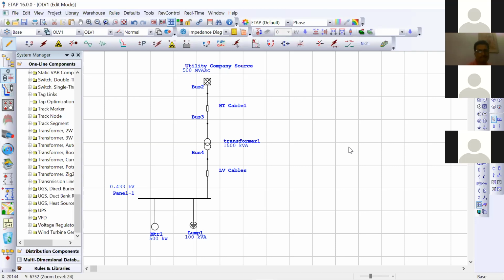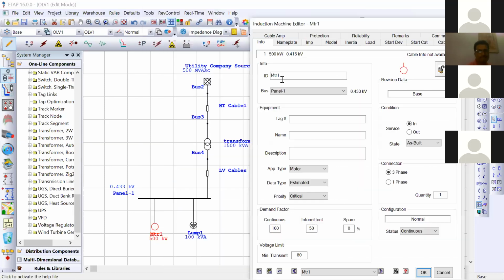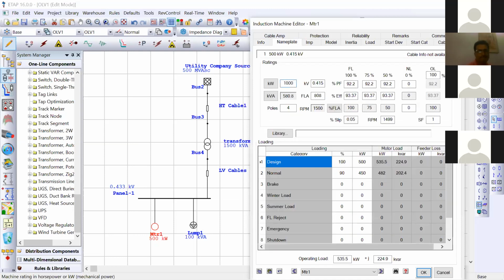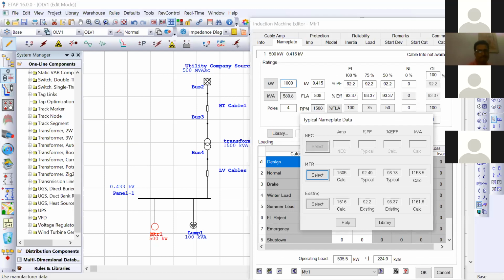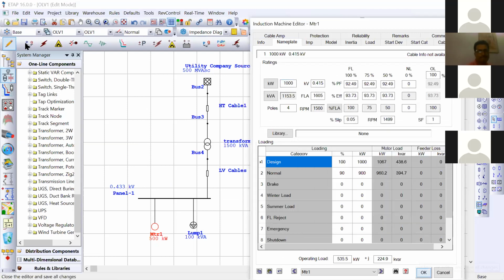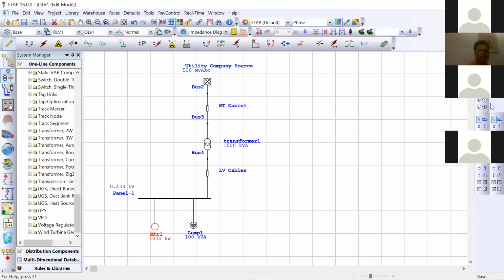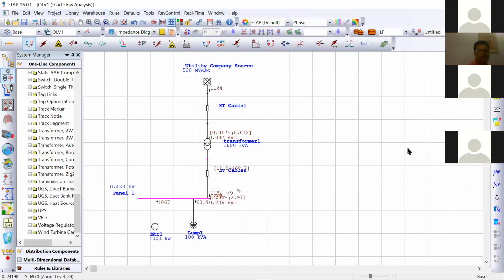So I was telling how ETAP will help you out. Since we have taken a small example, if I change the rating of this motor, presently we have performed the calculation using 500 kilowatt. If I change to say 1000 kilowatt, what is going to happen? If we want to check, then again we will perform load flow on this. I have deliberately taken a 1000 kilowatt motor. Now the system dynamics are changed.